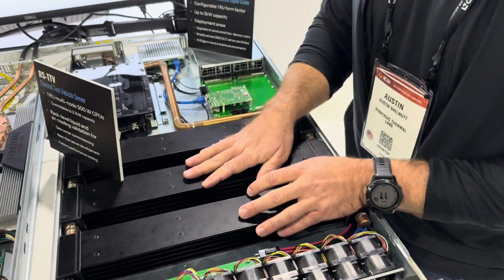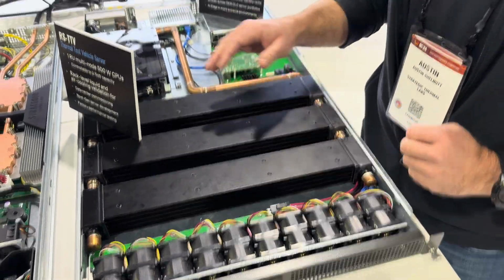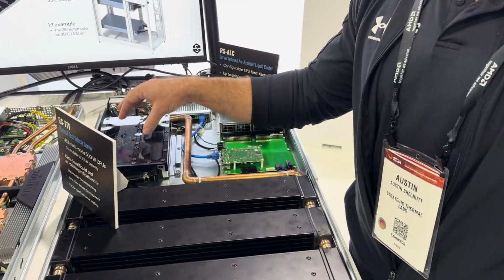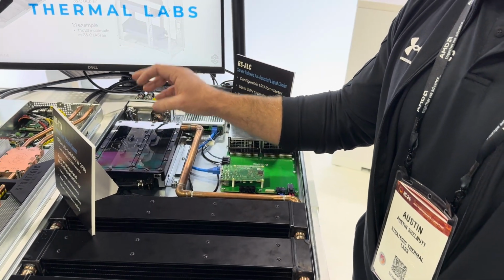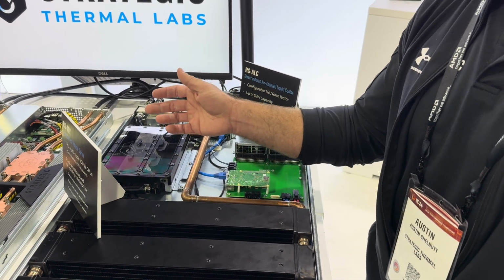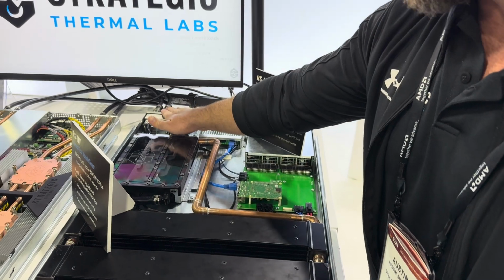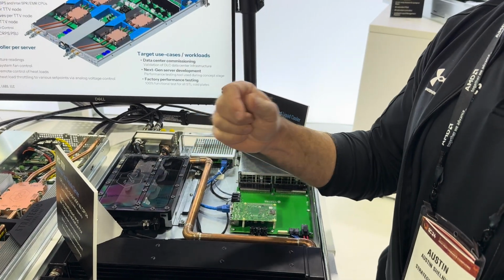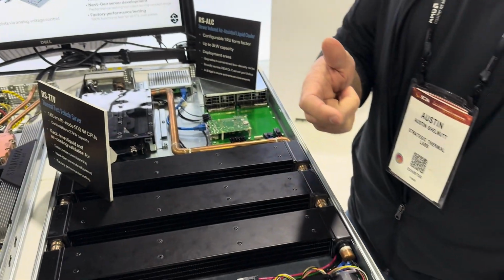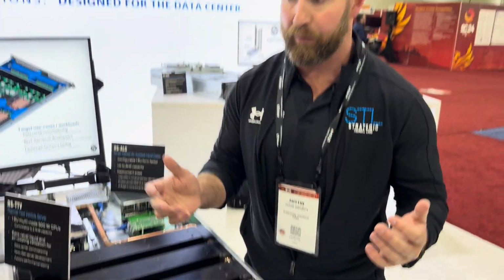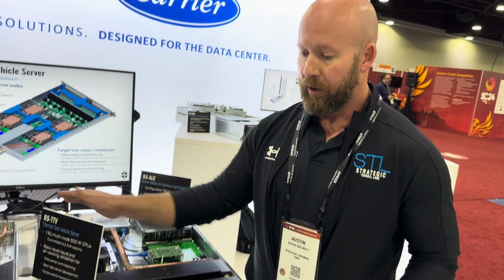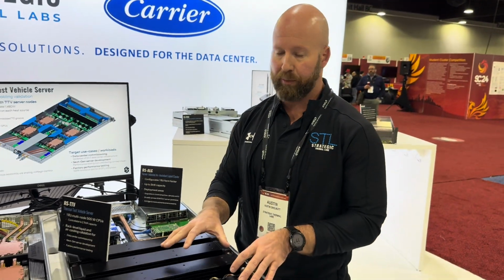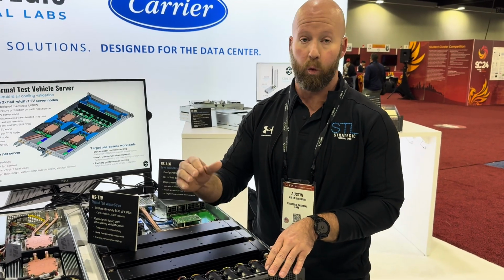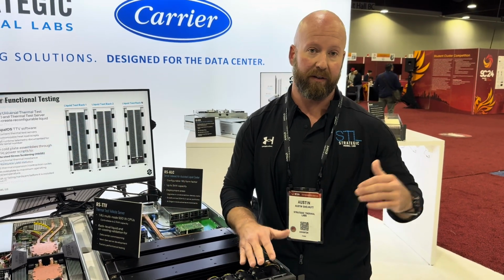It's got liquid air heat exchangers, N+1 fans. We have an N+1 pump reservoir module here that uses 3 pumps, so we can have a 2+1 configuration, and an integrated flow manifold in the back. So any liquid-cooled server that you buy that has common quick disconnects, like UQD as an example, will plug directly into this module. We can scale these up and have multiple ALC devices for one server, in an example where you have a very high-powered server, or we can go the other direction. We can have multiple servers put into one of these boxes.